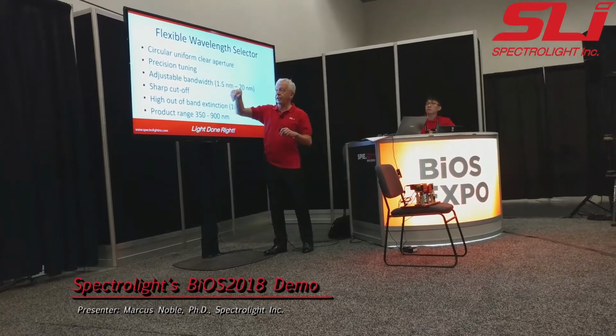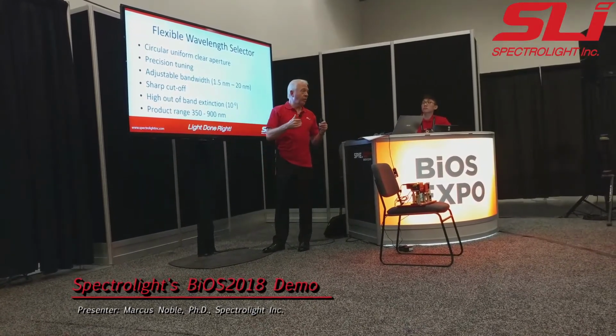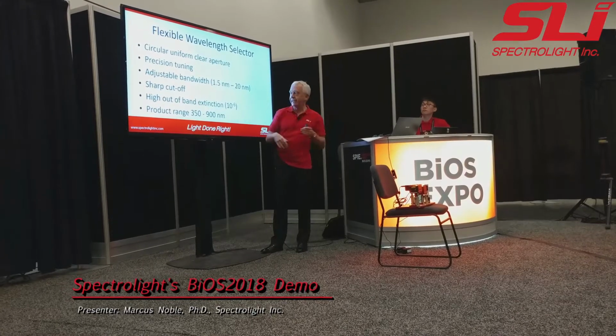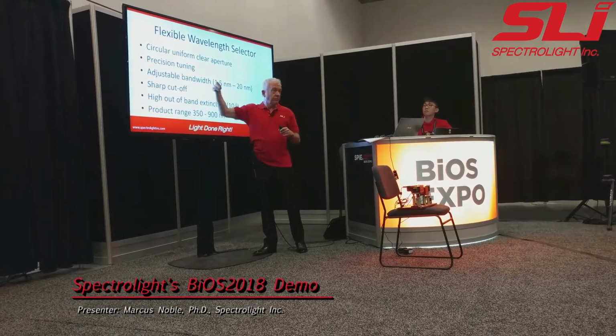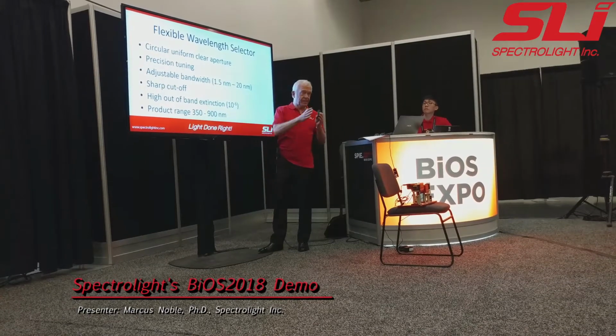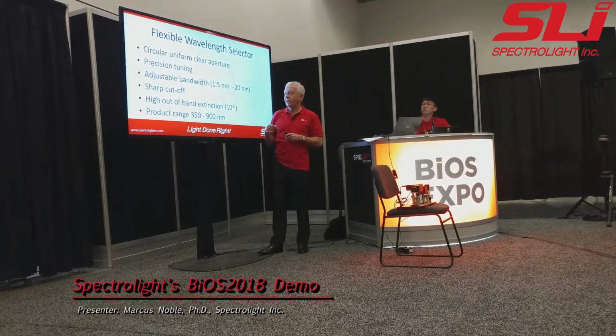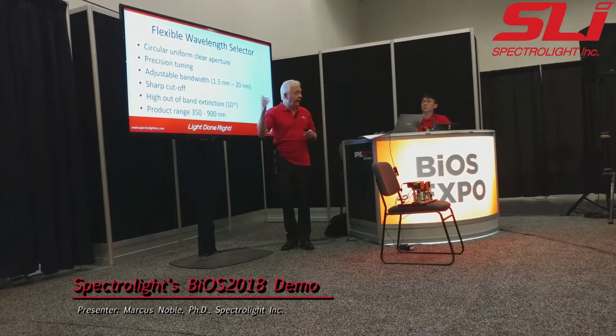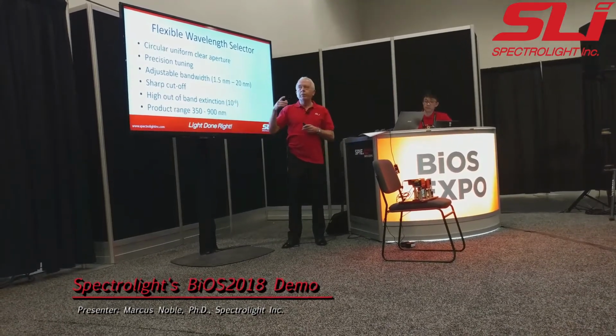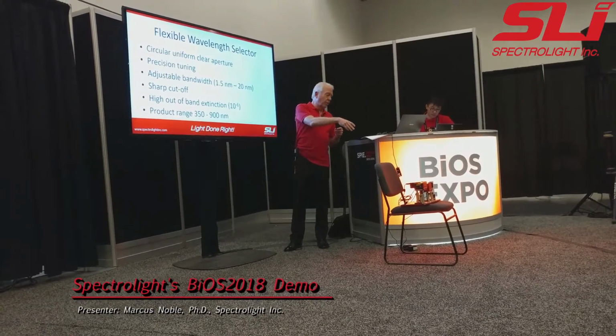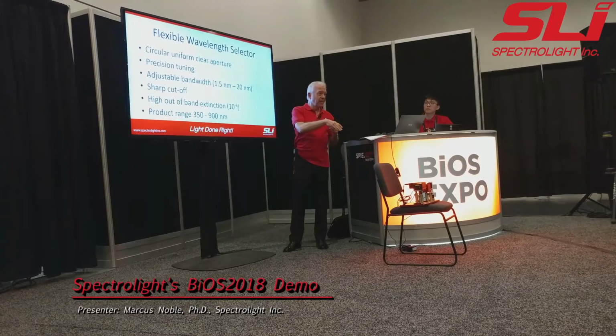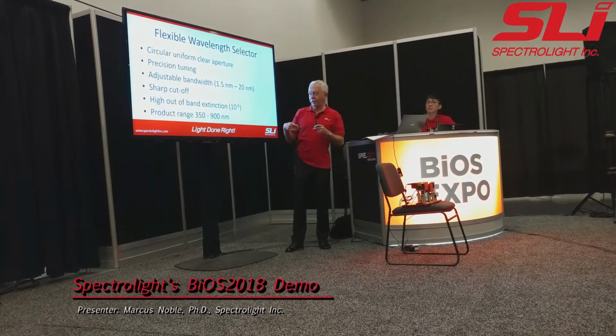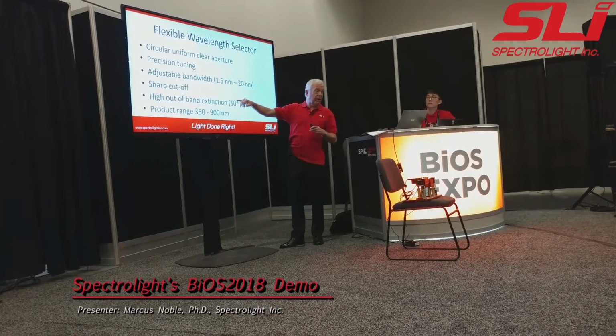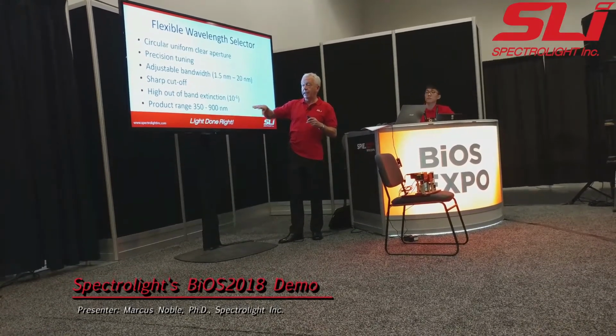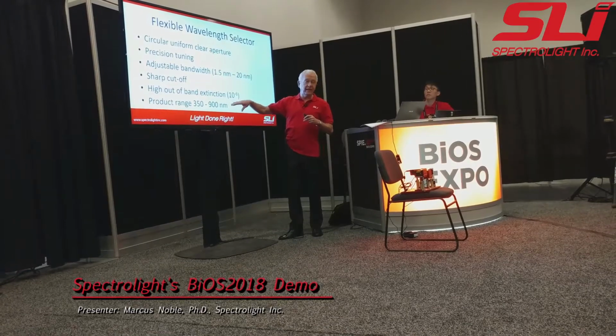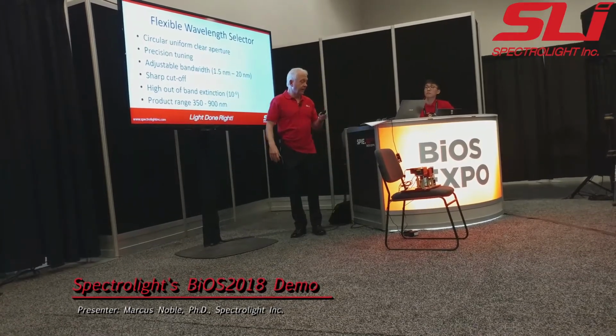So we've got precision tuning, adjustable bandwidth, just like you would with a monochromator where you could vary the slits or rotate the grating. Sharp cutoff, which is very important if you're looking at things that have a narrow emission or a narrow excitation spectrum. High out of band extinction. People have tried to do what this does before with things like AOTFs and other technologies, and there's often bleed through from overtones and so forth. This has got very high out-of-band rejection, 10 to the 6. And the entire product range covers the extended visible, 350 to 900 nanometers.